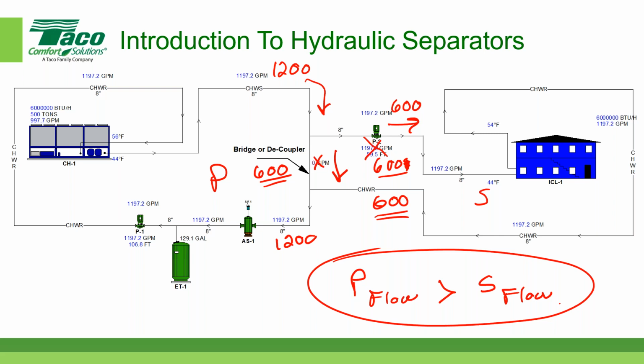Okay, all right. So Rick is asking, is there a way to verify what's across the bridge? Well, if you put in a flow meter, you can find out what the flow is across the bridge. You could put a flow meter in the bridge itself, or you could put it into the primary circuit. Let's say I put a flow meter over here, flow meter FM, and I also put a flow meter in the secondary circuit, down here, FM. So the difference between those two would be what's going across the bridge. Now, as long as the primary circuit was greater than the secondary circuit, the flow would be, in our case, horizontally and vertically down in our little diagram.